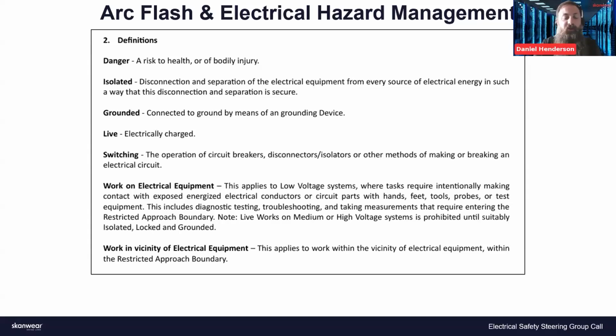If you're trying to make a difference in voltage, some of the differences are, US would be LV 600 volts, UK 1000 volts AC. And then there's that definition between low voltage, medium voltage, high voltage. A lot of equipment, low voltage might be 600 volts AC, but a lot of generation, things like wind turbines, solar PV, a lot of that generation's at 690 volts AC, so it already creeps into that MV category within the US, whereas in UK, Europe it would be in the LV bracket because it's under 1,000 volts AC.